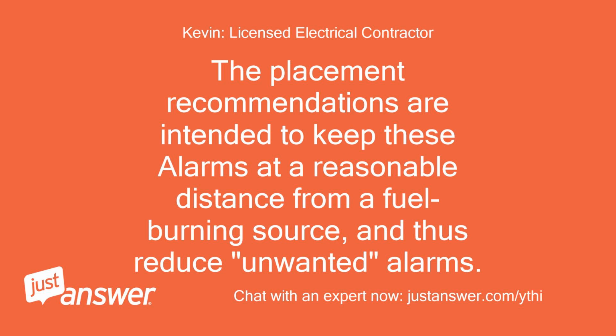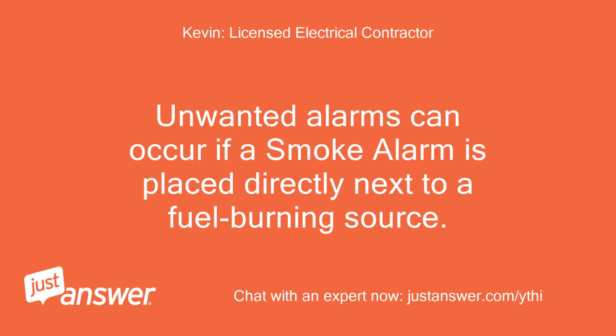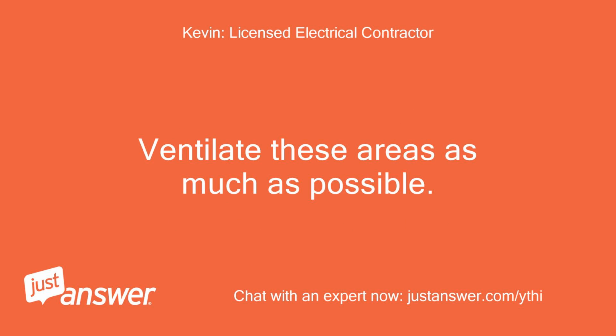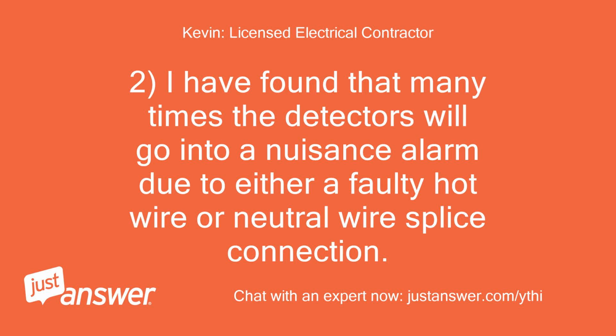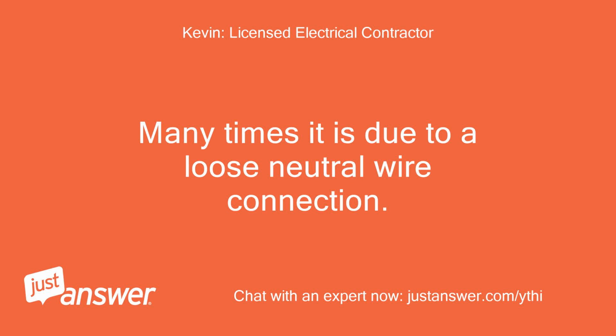The placement recommendations are intended to keep these alarms at a reasonable distance from a fuel-burning source, and thus reduce unwanted alarms. Unwanted alarms can occur if a smoke alarm is placed directly next to a fuel-burning source. Ventilate these areas as much as possible. 2. I have found that many times the detectors will go into a nuisance alarm due to either a faulty hot wire or neutral wire splice connection. Many times it is due to a loose neutral wire connection.